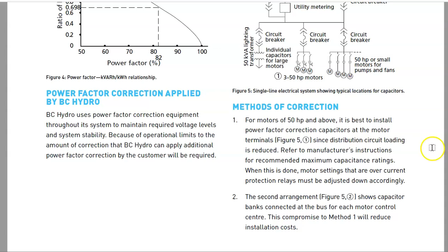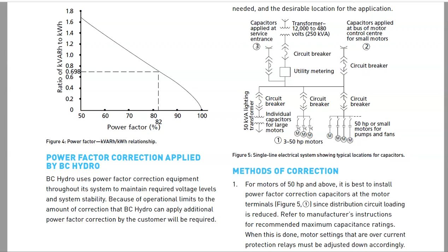The second place is where I'm going to have it connected for a bus. So they talk about this over here where I've got multiple smaller motors that add up to become about 50 horse, and I'm going to bus connect. In other words, when this bus gets energized, I'm going to energize that cap over there. There is danger, though, that if each of these small motors get shut off and this cap stays on, I could end up with a leading power factor.